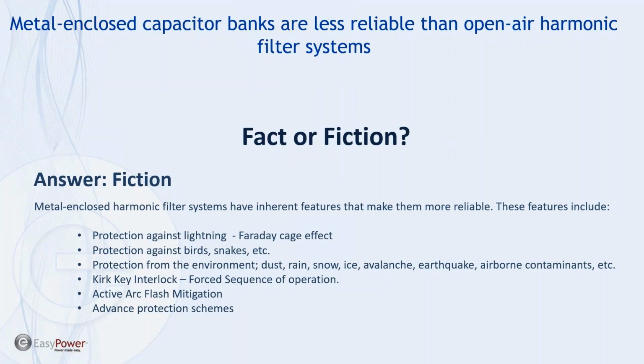And really what was going on at the time is that the iron core reactor suppliers did not understand the impact of harmonics on their reactors. They didn't understand how the harmonics heated the iron cores up. The designers of the harmonic filters did not account for enough margin in their design. And as a result, there was an abundance of reactor failures. I'm saying going back to the 1980s. But if you go forward to the present day, the reactor suppliers who are in the business have many, many years experience, and their ability to build a reliable reactor is not difficult at all.